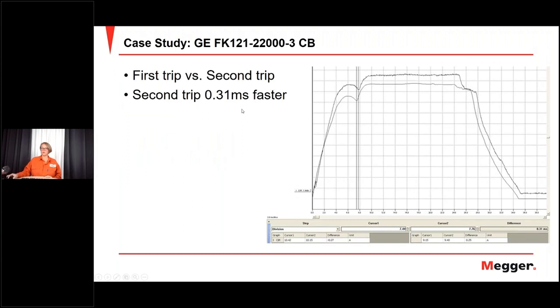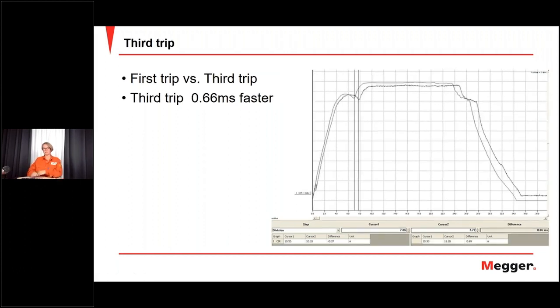Here we have a case where we only look at the current in the control circuit, and still we have interesting information. You can see that they are different in the operation time because you have different armature time here. And the delay is 0.3 faster during the second time you operate the circuit breaker. And he did it a third time and it was 0.66 milliseconds faster. So you directly can see that these are things that are influenced by the single operations. The operations make the circuit breaker quicker. So there was no service in between, it's just the operation that has trained the circuit breaker to become faster because the different links have been operating towards each other and work smoother.